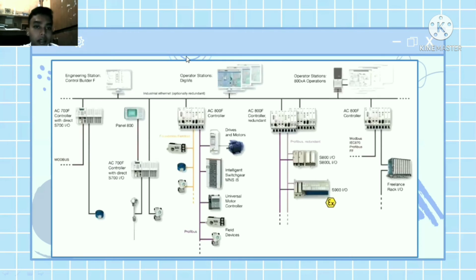Number 4 is the communication system. The communication medium plays a major role in the distribution control system. It interconnects the engineering station, operation station, process station, and smart devices with one another, carrying information from one station to another. Common communication protocols used in DCS include Ethernet, Profibus, Foundation Field Bus, DeviceNet, and Modbus.